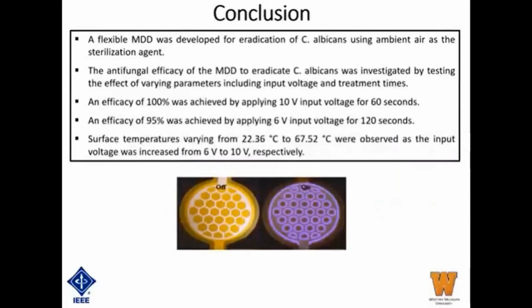As a conclusion of this work, I would mention that here in this work, a flexible microplasma discharge device was developed for eradication of Candida albicans using ambient air as a sterilization agent. The antifungal efficacy of the microplasma discharge device to eradicate Candida albicans was investigated by testing the effect of varying parameters, including input voltage and treatment times. An efficacy of 100% sterilization was achieved by applying 10 volts input voltage for 60 seconds. And an efficacy of 95% sterilization was achieved by applying 6 volts input voltage for 120 seconds.